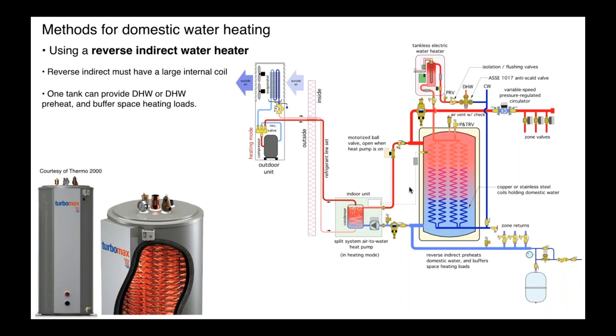Okay. We're also showing here one of the things you don't want to do with any heat exchanger, and certainly this applies to the condenser in an air to water. You don't want to have any debris going into that heat exchanger. So a good dirt separator, a magnetic equipped dirt separator is good, especially if you're using high efficiency brushless DC circulators in the system. We want to capture any oxides, iron oxides, and get those out of the system before they go in, potentially scale out on that heat exchanger.